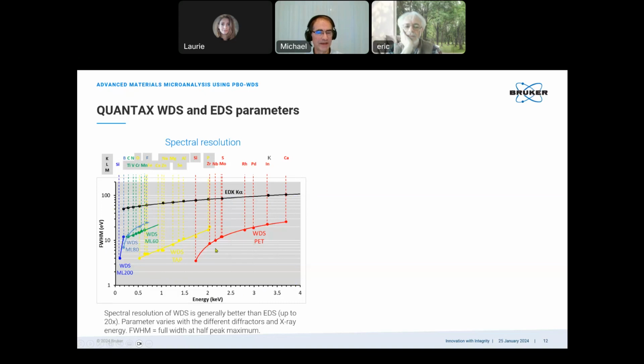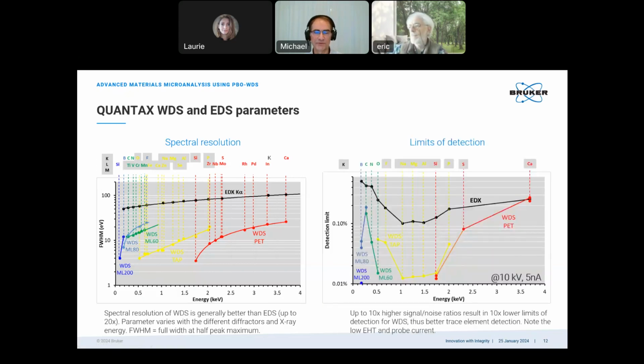The half width depends on the energy of the X-rays, but also on the different analyzer crystals. And this is shown here. PET is one, TAP is one, and here multi-layer elements with different angstrom lattice spacing. So to cover the entire energy range, we need these different diffractors, and they show different properties. In conclusion, what we can see from this graph, the resolution of the WDS is much higher, up to 20 times higher. For example, the silicon K alpha is 3.5 electron volts for the WDS system and 70 electron volts for the EDS system. So we can much better resolve overlaps.